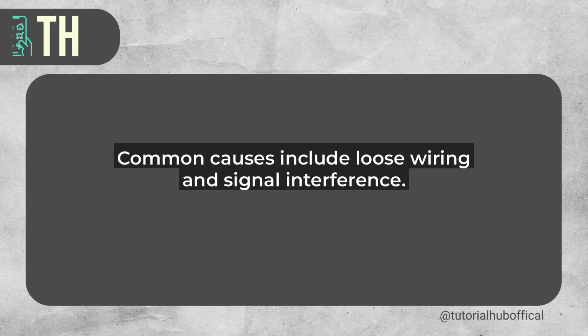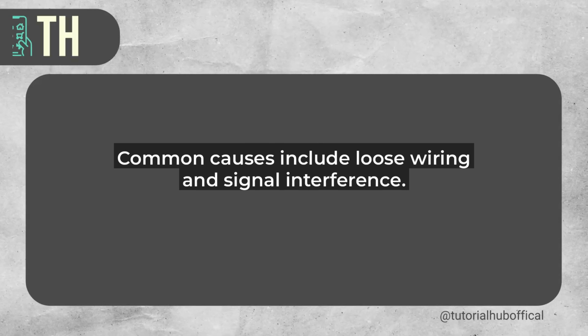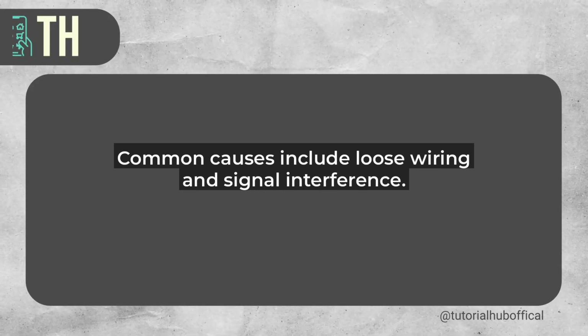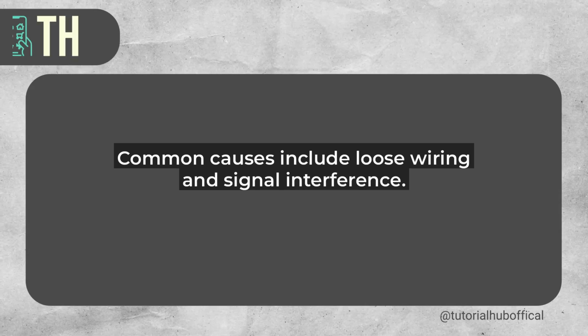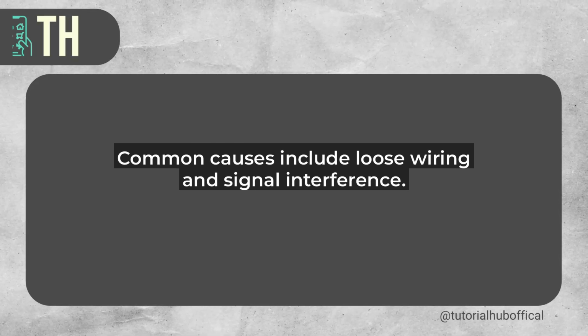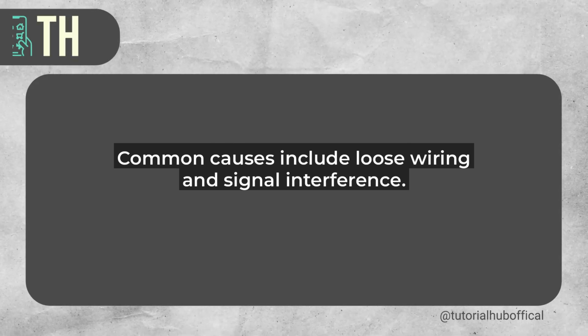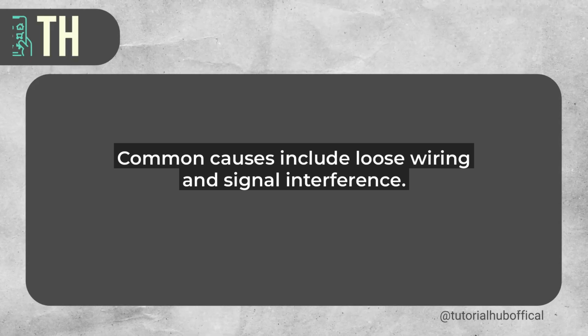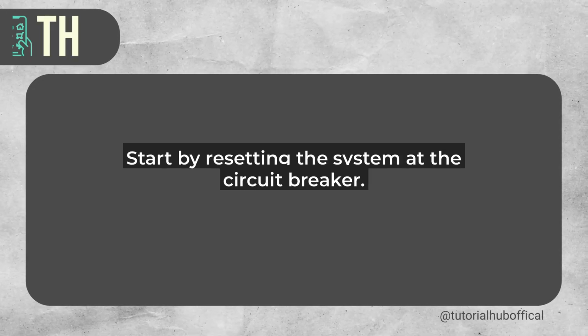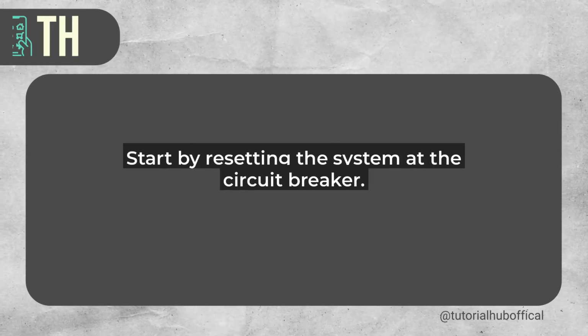First off, let's understand what this error means. The E-201 code typically indicates a communication error between the indoor and outdoor units of your Samsung VRF system. This could be due to issues with the wiring, signal interference, or even a faulty control board. It's like your AC units aren't talking to each other properly, which can lead to the whole system shutting down.